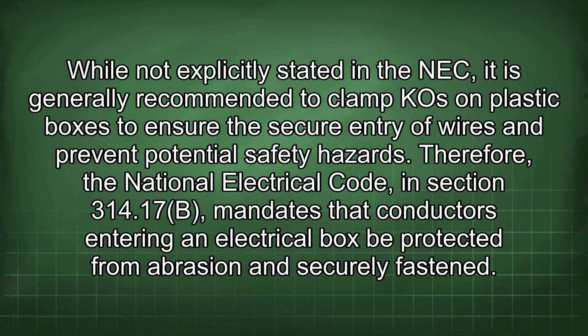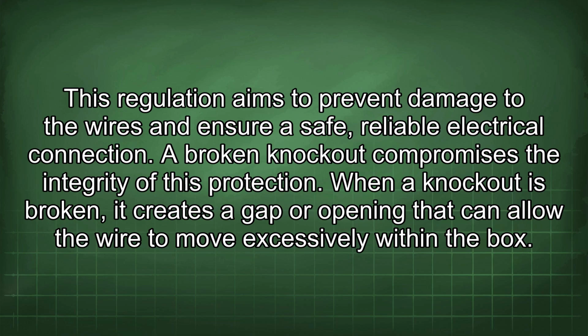Therefore, the National Electrical Code, in Section 314.17(B), mandates that conductors entering an electrical box be protected from abrasion and securely fastened. This regulation aims to prevent damage to the wires and ensure a safe, reliable electrical connection. A broken knockout compromises the integrity of this protection.